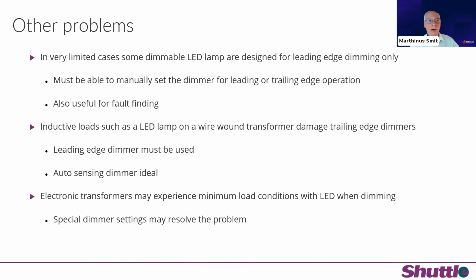Very importantly, inductive loads, especially with LED lamps, such as transformers and so on, we still do find out there, because there are retrofits from old installations and they change to 12 volt LEDs, and invariably, in a dirty ceiling somewhere, somebody forgets to take out the transformer. Now that huge inductive load can actually damage your trailing edge dimmer, and in some cases it can also cause damage to LED lamps. So in that case, a leading edge dimmer must be used, and ideally your dimmer must be auto sensing.